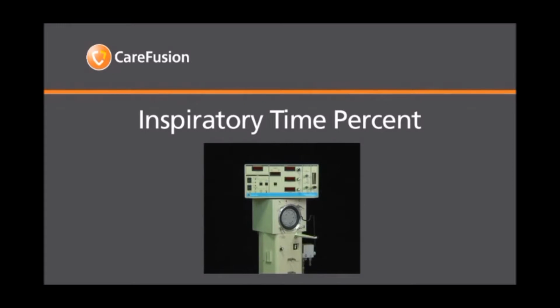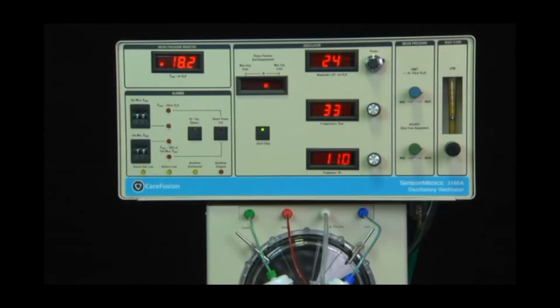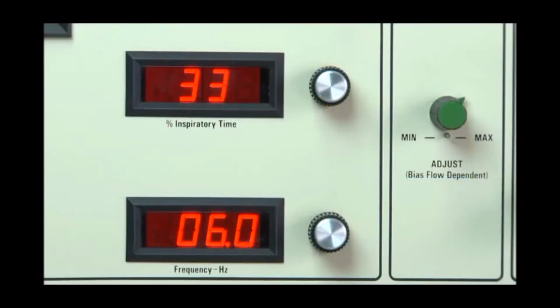Inspiratory time percent. The inspiratory time percent sets the relative duration of the successive positive and negative polarity voltages from the square wave driver. Since this parameter is set as a percent of cycle time, absolute inspiratory time is a function of oscillatory frequency and inspiratory time percent. For most applications, this parameter remains at 33%.